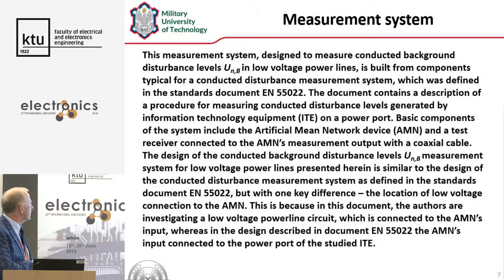The design of the conducted background disturbance level measurement system for low voltage power lines presented in my article is similar to the design of the conducted disturbance measurement system as defined in this standard, but with one key difference: the location of the low voltage connection to the artificial mains network. This is because in my paper the authors are investigating low voltage power circuits, which are connected to the artificial mains network input. Whereas in the design described in the standard, the power port of the studied information technology equipment is connected to the artificial mains network input. So my goal is to measure the disturbance at the output of the power line instead of the output of the equipment under test.